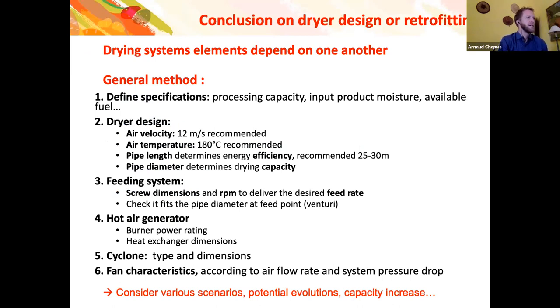So finally, an important comment is that when you want to design a new dryer or retrofit an existing dryer, it's important to consider the whole system, because all the elements depend on one another. If you change the blower to have a higher airflow rate, probably you will have to adapt your heat exchanger also, because your heat exchanger will not give the right temperature if you double the airflow rate.